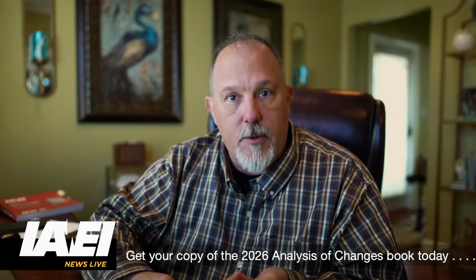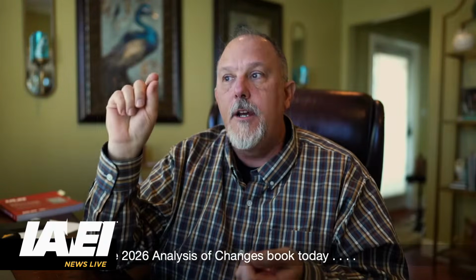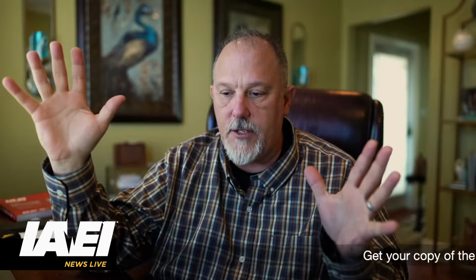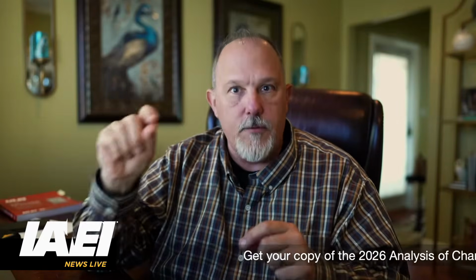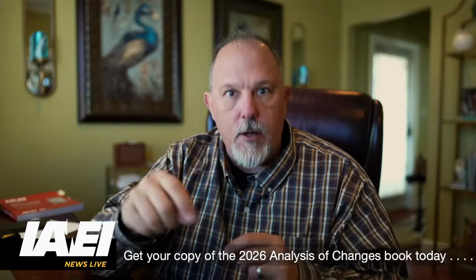If you didn't see last week's, you've got to go check it out. But identified is when the manufacturer's instructions will tell you, hey, if you want to put a handle tie on here, go buy this catalog number. Because you can't put an ABB handle tie on an Eaton breaker or a Siemens handle tie on an ABB breaker, and vice versa and all that jazz. So it's important to make sure that we have the right solution for the product.